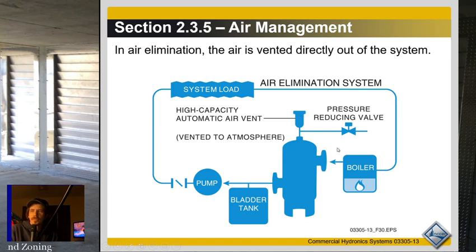Pipe these over to a drain, okay? Save everybody some headache and pipe these things over to a drain, so that you don't end up with water all over the insulation and everything in there when it starts to fail. It's very nice to pipe these things out over to a drain. They just vent the air out to the atmosphere.